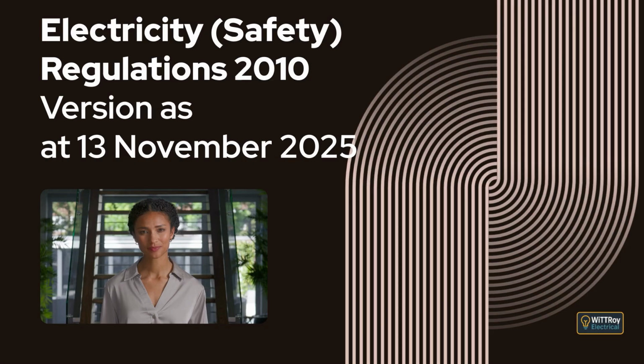The installation must have a maximum demand at or below 80 amperes per phase for single phase, or 50 amperes per phase for multi-phase. The regulation then explains the types of work covered. This includes things like removing and replacing fuse links, connecting and disconnecting fixed wired appliances, and relocating existing switches, socket outlets, and lighting outlets that are supplied by tough plastic sheathed cables.